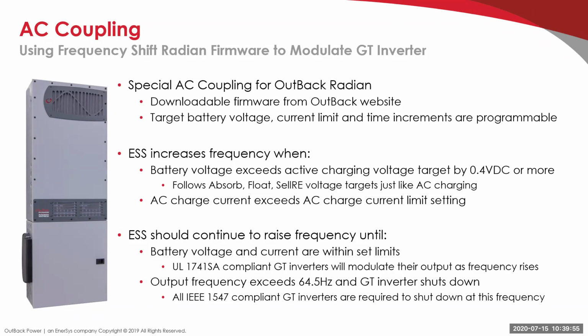So we do kind of the same thing. When we start increasing the frequency, a UL 1741 SA set up for Rule 21, and you have to do this, you have to go in your grid-dependent inverter and set it up for Rule 21. Make sure you set it up for the one that has the frequency that goes up to 62 hertz, not 60.5. And as we shift the frequency up, the grid-dependent inverter starts lowering its output.